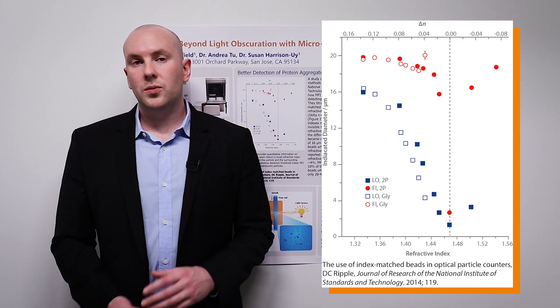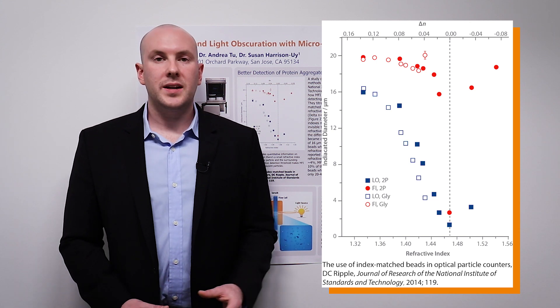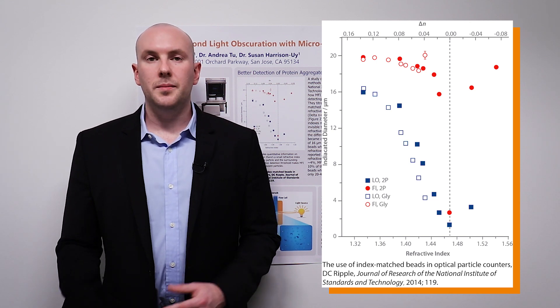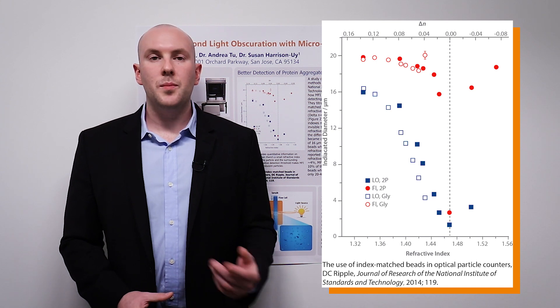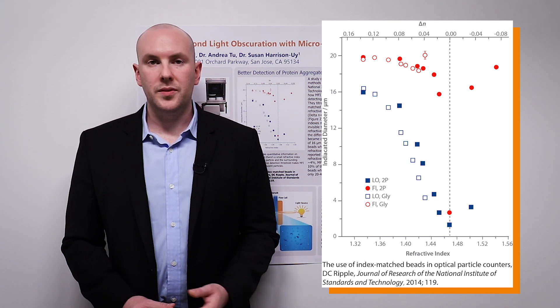As you move left from that dotted line, you begin to see the measurements taken by the two technologies diverge. At only a 4% difference in refractive index between the beads and the matrix, MFI is already measuring within 10% of the nominal diameter of the beads, whereas light obscuration measurements are only coming in at about 25% of the total diameter. So MFI is measuring about 18 microns compared to the nominal diameter of 20 microns, while light obscuration is only measuring 5 microns under those same conditions.